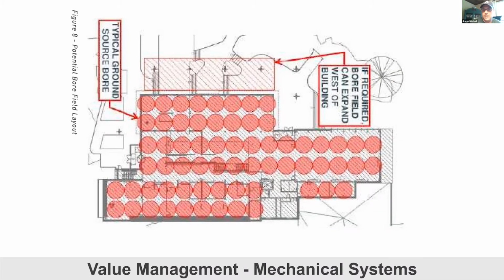Because of the limit of disturbance restriction of the Living Building Challenge, these wells really needed to be underneath the building. So we had one that was a 500 foot deep geothermal well option. Ultimately, it lost out to the campus chill water loop because the chill water loop lines went right through the neighboring street. It was super close, only about 40 feet away from our chillers.